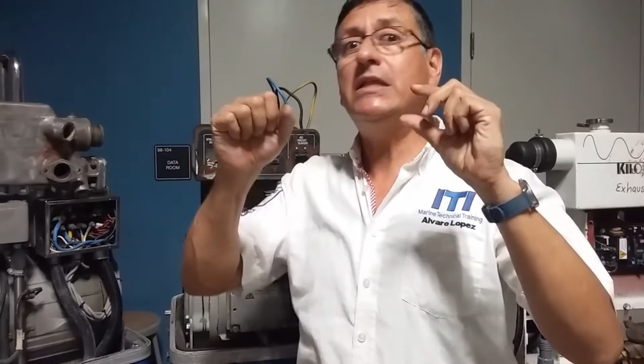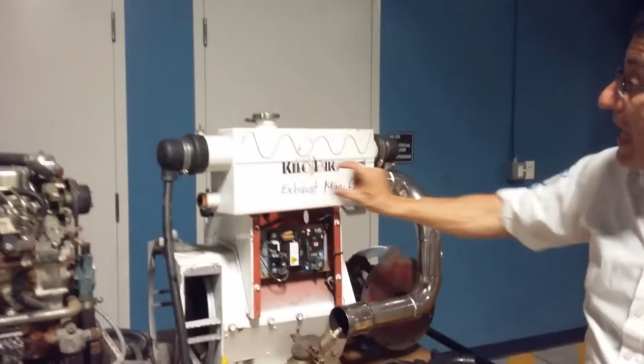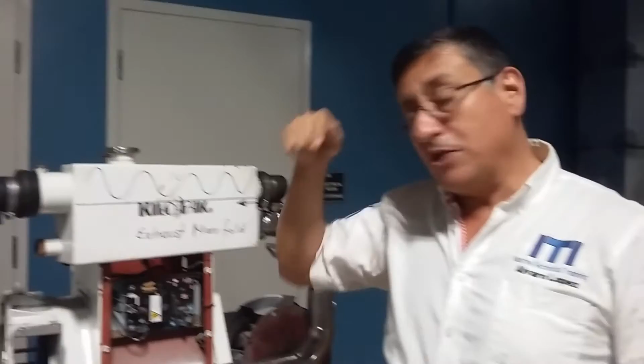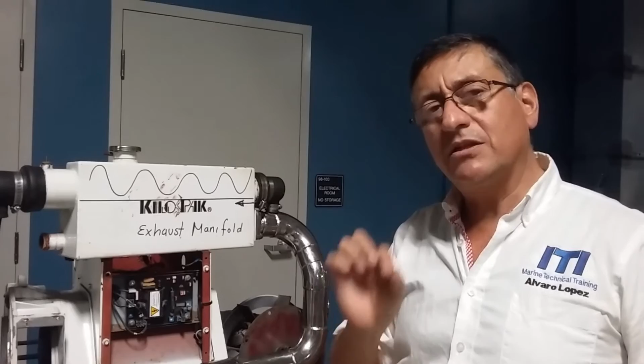You remember what happens during the intake stroke? During the intake stroke, only the intake valve opens, and the exhaust valve should be closed. When the piston is going down, the air enters. What happens if the exhaust valve is a little open because it's improperly calibrated? When the piston is going down, it suctions water, because you have salt water here and gases over there. For that reason, the majority of the diesel generators need to calibrate the exhaust valve every 250 hours.